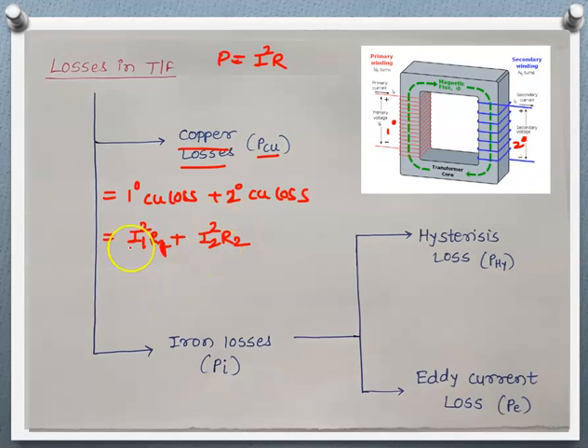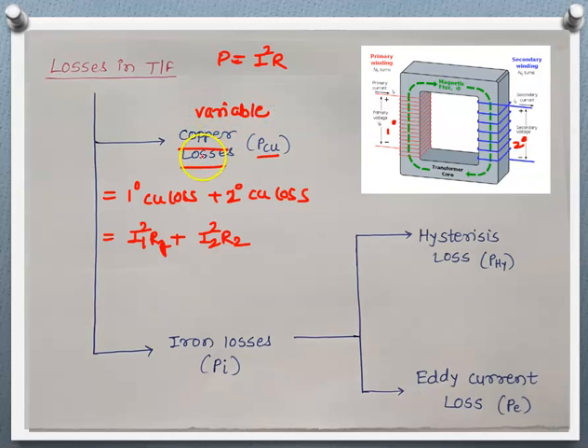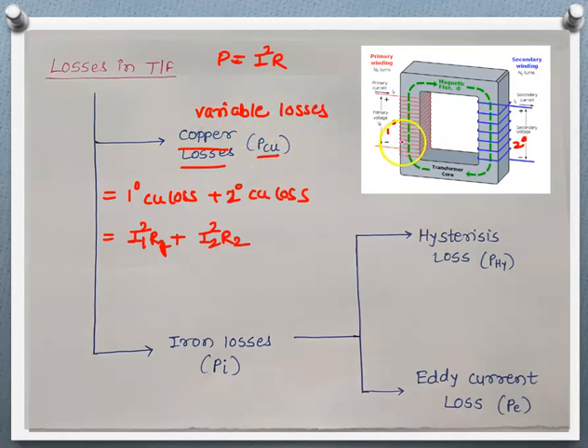Copper loss depends upon I1 and I2 values because R1 and R2 are constant, but I1 and I2 depend upon the load. As the load changes, this value changes. So copper loss is also known as variable losses because its value depends upon the load. To reduce copper losses, we prefer low winding resistance of the primary and secondary winding, so that the efficiency of the transformer will be better.